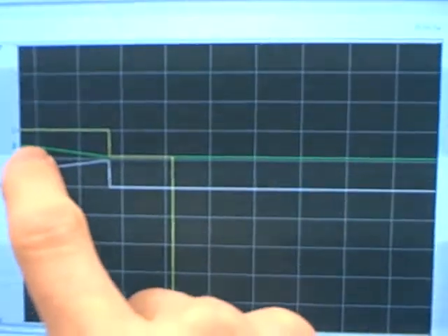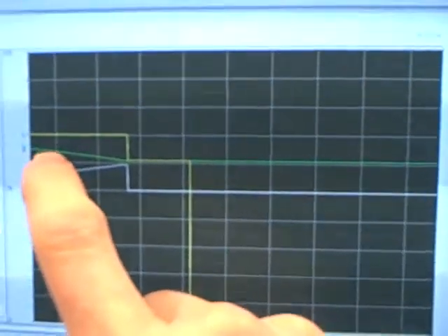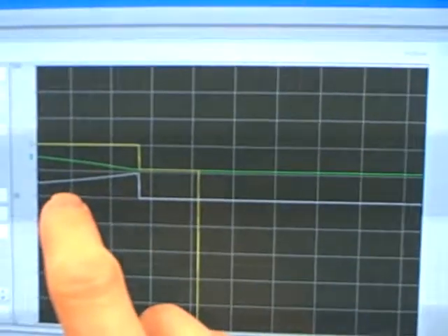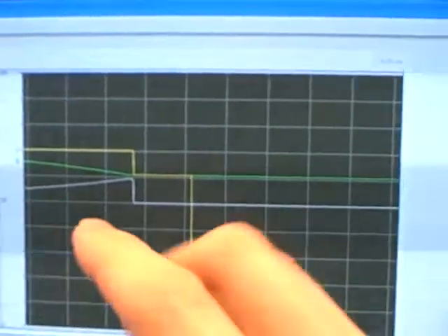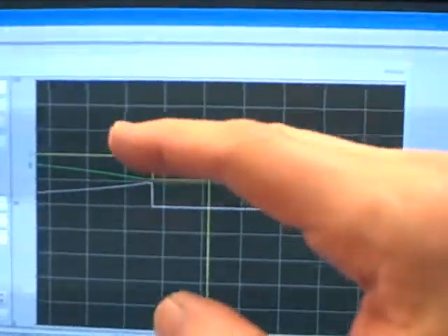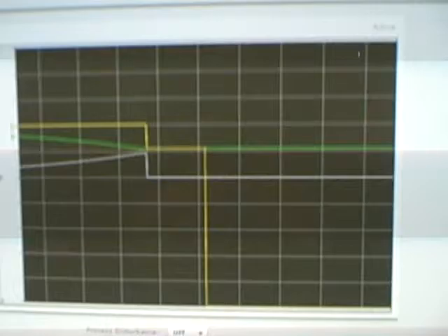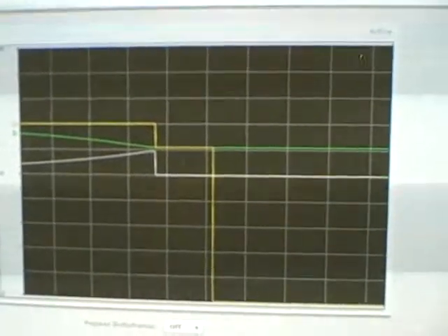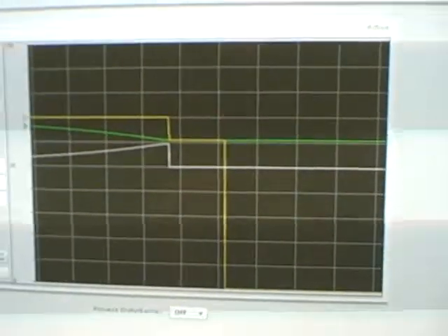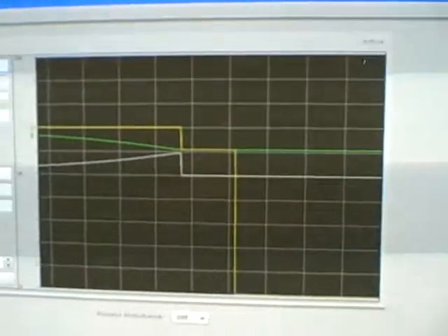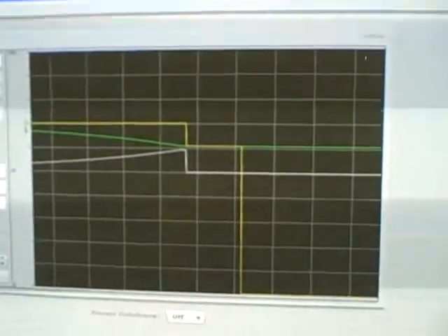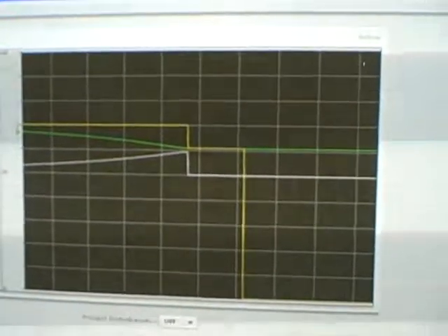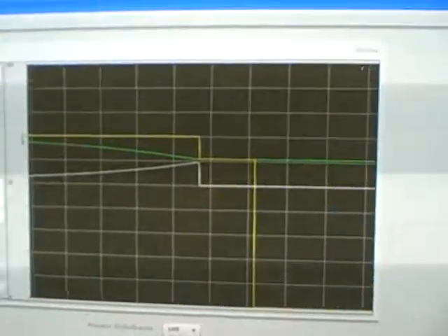And as the liquid level rises and gets closer to the new set point value, we see that the output will slow down and we just basically ease into the new set point value. It's going to take a while because we don't have very aggressive gain in this particular tuning. We only have a gain of 1. So we will get to our new set point, but it's going to take a long, long time to get there. What will help us out is a more aggressive gain value.